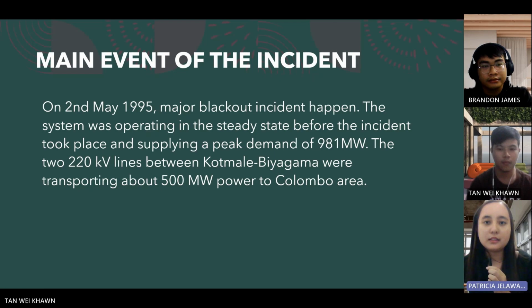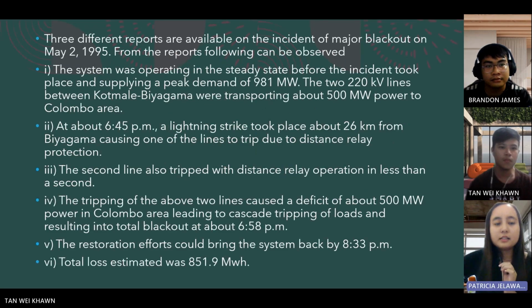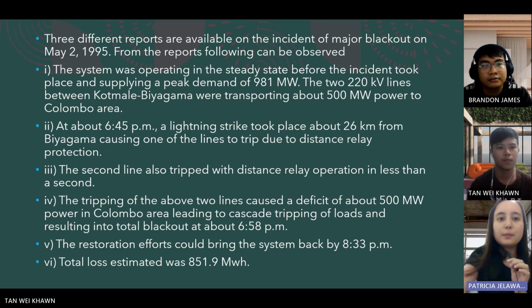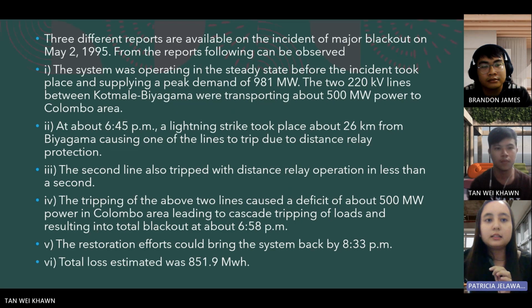As for the main event of the incident, on 2nd May 1995, a major blackout accident happened. The system was operating in the steady state before the incident took place and supplying a peak demand of 981 megawatt. The 220 kV lines between Kotmale and Biyagama were transporting about 500 megawatt power to the Colombo area. This is the chronology of what happened. 3 different reports are available on the incident of the major blackout on May 2nd, 1995. From the reports, the following can be observed. The system was operating in the steady state before the incident took place and supplying a peak demand of 981 megawatt. The 220 kV lines between Kotmale and Biyagama were transporting about 500 megawatt power to the Colombo area.